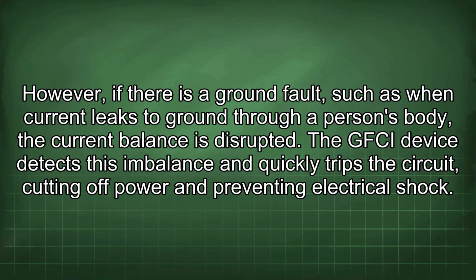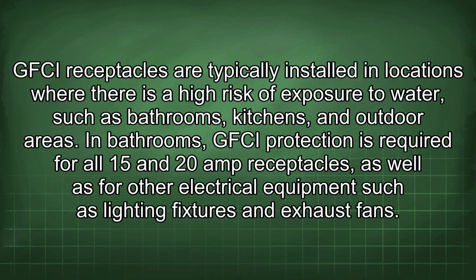The GFCI device detects this imbalance and quickly trips the circuit, cutting off power and preventing electrical shock. GFCI receptacles are typically installed in locations where there is a high risk of exposure to water, such as bathrooms, kitchens, and outdoor areas. In bathrooms, GFCI protection is required for all 15 and 20 amp receptacles, as well as for other electrical equipment such as lighting fixtures and exhaust fans.